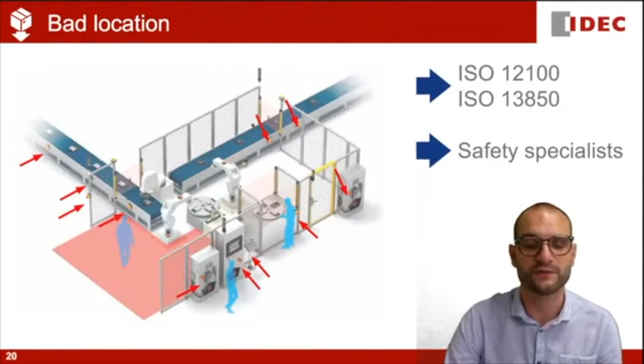Now let's see what we can do to avoid and detect the bad mounting. The first option available on the market is the self-monitored contact block. It is a contact block that detects the presence of the operator. There are two contacts in series. The usual normally closed contacts stops the machine when the e-stop is pressed, and a normally open contact that operates with the presence of the operator.